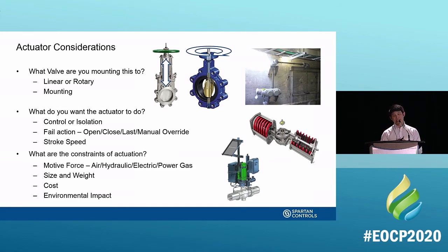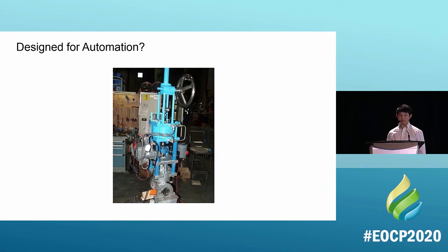And then the next thing is, is my valve manufactured to be mounted? Can I mount an actuator easily to this? So a lot of the times when we look at valves and we haven't thought about it well, we get something like this. In my office, we call this a Christmas tree because it's where someone purchased a valve. They didn't think about what actuator they were going to put on it. They didn't think about the functionalities. They didn't ask themselves these three questions.